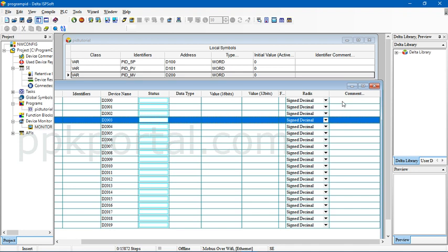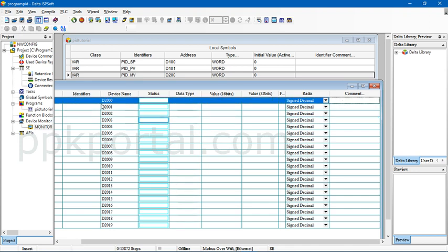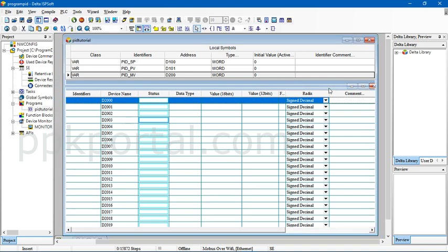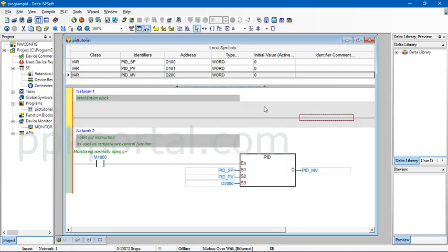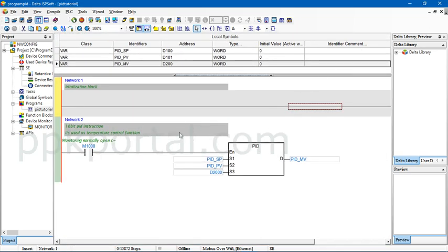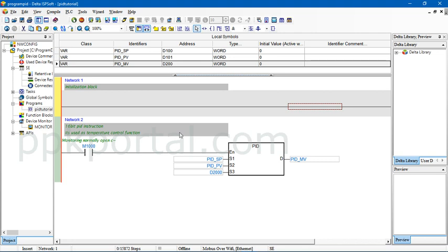If you have already worked with Delta PLC, we have the temperature thermocouple and PT100 module which are available for measuring temperature. They give the value with precision of 0.1 degree Celsius. So if the temperature is 32 degrees, the value which we will get using the FROM instruction will be like 320. If the temperature is 20 degrees, the value will be 200.